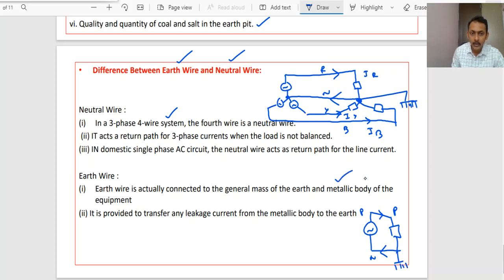It is provided to transfer any leakage current from the metallic body to the earth. If any leakage current is there, that current will pass through the earth wire to the grounding system, and this grounding system should have a very low value of resistance. If it offers a high resistance, then this current cannot pass through the earth wire to the grounding system. For this sake we make all those arrangements to reduce the resistance of the earthing system. It should be as low as possible, right?